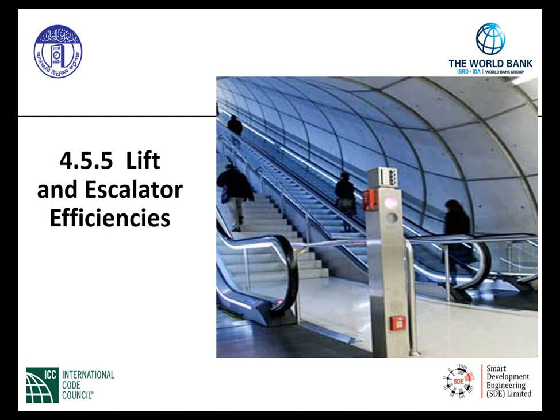One, reduce speed control. The escalator shall change to a lower speed when no activity has been detected for a period of up to 3 minutes. And detection shall be a photocell activation at the top and bottom landings, or the use on demand. The escalator shall shut down when no activity has been detected for a period of up to 15 minutes, designed with energy efficient soft start technology. It takes a lot of energy to start and stop things. And so it's saying use that soft start technology that gets it going. Might be a little slower, but it doesn't use as much energy. The escalator shall start automatically when required, and activation shall be photocells installed at the top and bottom of the landings. We're going to see in a little bit how this ties into a different section of the code. It has the same requirements, maybe goes into a little more detail later on, but they tie in together.